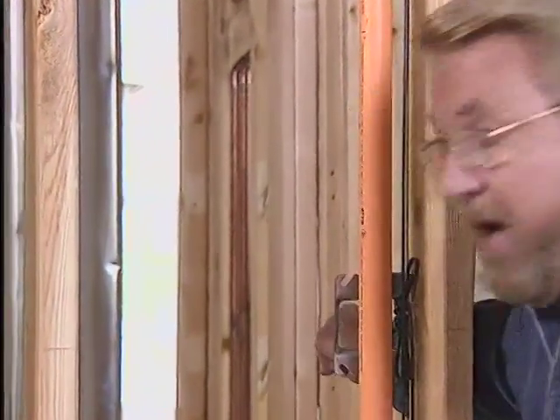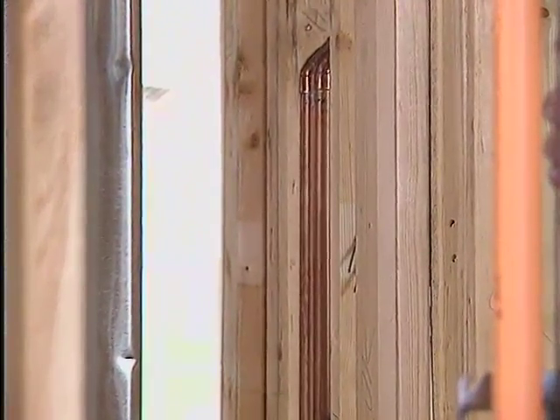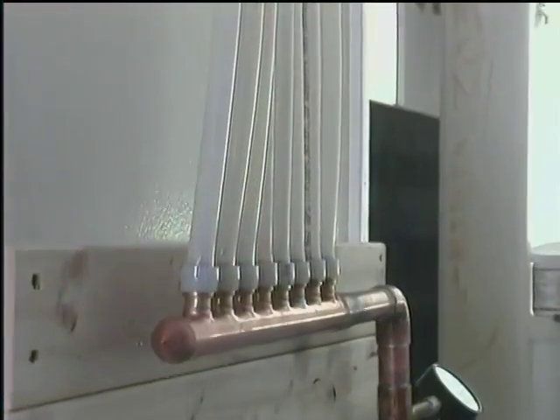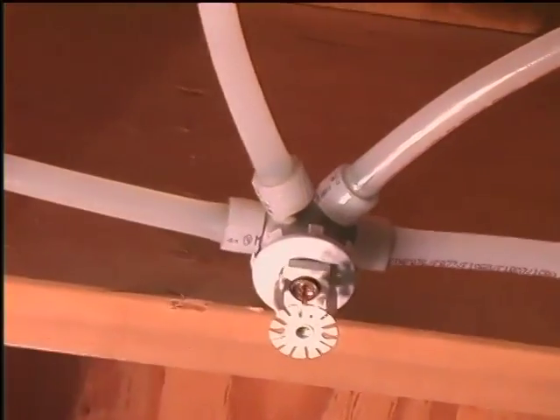There are two common types of fire sprinkler systems, both acceptable under NFPA 13D. The first is an independent or standalone system, and that's what's being installed in this house. Here, for example, you can see the plastic sprinkler pipe, and back there the copper pipe for the domestic water supply. The second is a multi-purpose or network system. This system feeds both the sprinklers and the cold water fixtures with the same pipes. What you notice is a large number of smaller pipes that run to various locations of the home, supplying the sprinklers and the cold water fixtures.